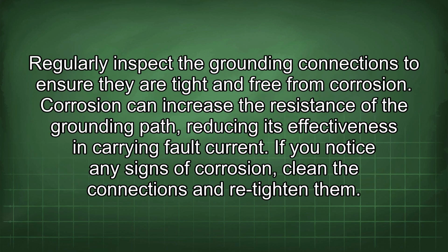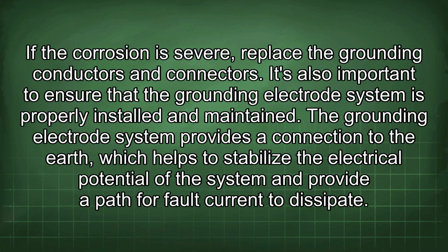Regularly inspect the grounding connections to ensure they are tight and free from corrosion. Corrosion can increase the resistance of the grounding path, reducing its effectiveness in carrying fault current. If you notice any signs of corrosion, clean the connections and retighten them. If the corrosion is severe, replace the grounding conductors and connectors.